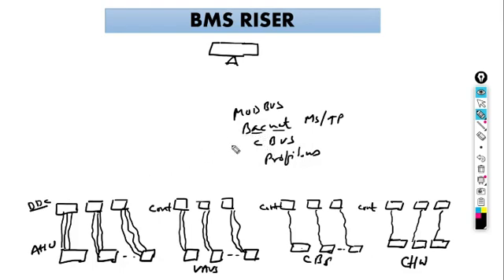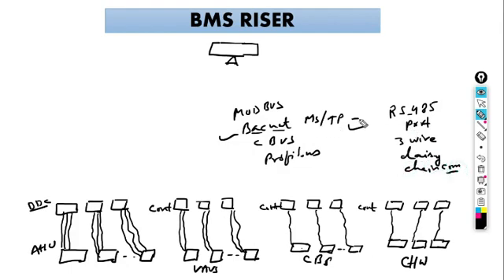Now we want to use BACnet over MSTP. This BACnet over MSTP uses an RS485 port. It is called a 3-wire daisy chain. I will show all the wires and connections in the next slide. This is a communication protocol, and it uses this topology, right? Topology is how they are going to be connected, and protocol is how they are going to talk.